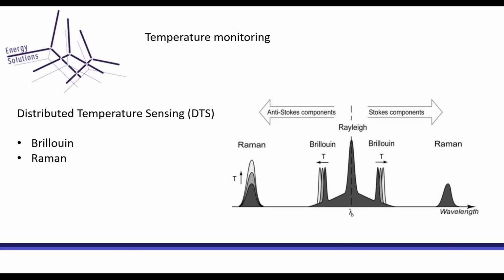But the better solution, which you can do with modern cables, is to use distributed temperature sensing. Distributed temperature sensing uses a fiber optic that is integrated in the power cable to measure the temperature response. And there are basically two technologies that are used in the industry: the Brillouin technology and the Raman technology. With the Raman technology, you basically send a laser pulse into the fiber optic, and you get some reflections which break up into two different wavelengths. One wavelength is not influenced by the temperature, but the other wavelength is. So if you have a different intensity, you have a different temperature, and in this way you can measure the temperature of the power cable along the complete cable length.